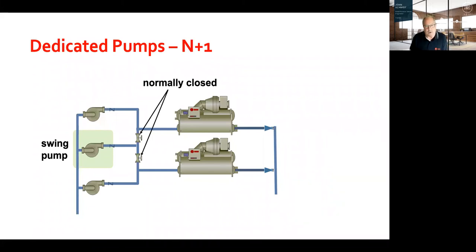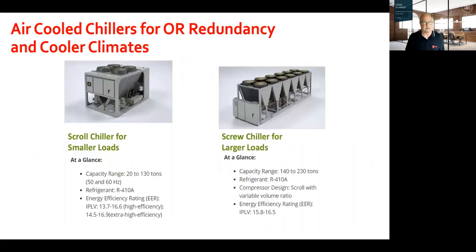But you also want to look at the pumps. You may want a swing pump, and that way your pumps are also redundant. So if you only had one pump per chiller, obviously even if the chillers are running and one of those pumps goes down, you're still going to be short on flow. So it's good to plan for another pump as a redundant pump, as well as the redundant chillers. Next slide.